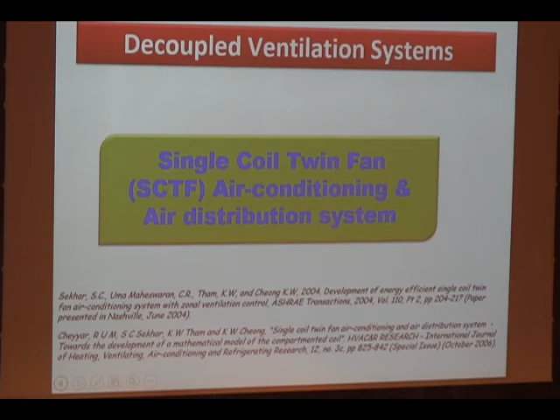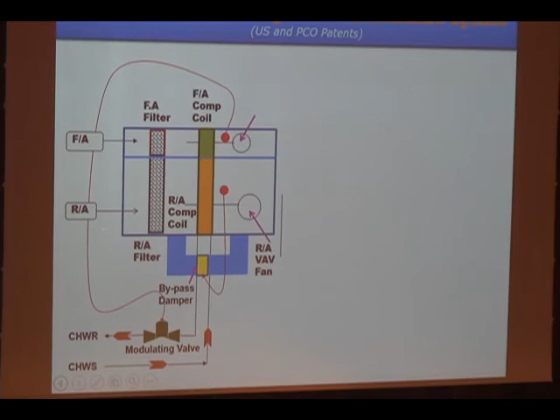So here is something, the single coil twin fan that we have worked on for several years now. It's one air handling unit, one cooling coil, but there are two compartments here. We have the outside air compartment. I'm sorry, I'm using the word fresh air. It's not fresh until it's filtered properly, so the right word should really be outside air, and this is the recirculated air. And as it goes through, we keep them separate until it reaches a zone where we have a way to manage these two air streams based on what's happening in that particular occupied zone.